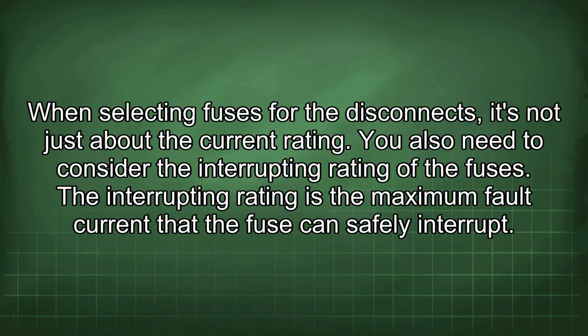When selecting fuses for the disconnects, it's not just about the current rating. You also need to consider the interrupting rating of the fuses. The interrupting rating is the maximum fault current that the fuse can safely interrupt.